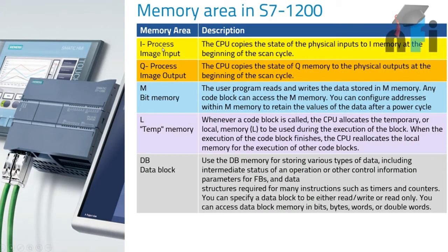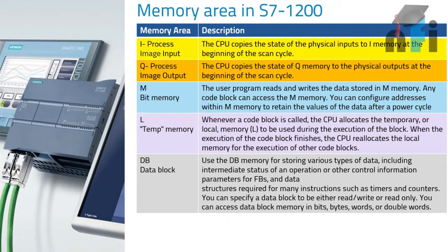First is process image input. We have a special memory allocated for inputs — this memory area is dedicated to inputs, which will read the status of inputs and store their status in memory. The CPU copies the state of physical inputs to I memory, which is the input process memory, at the beginning of the scan cycle.